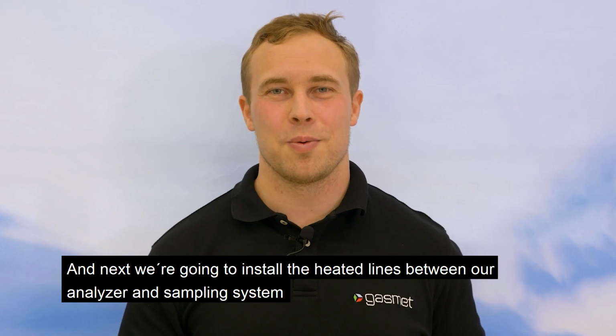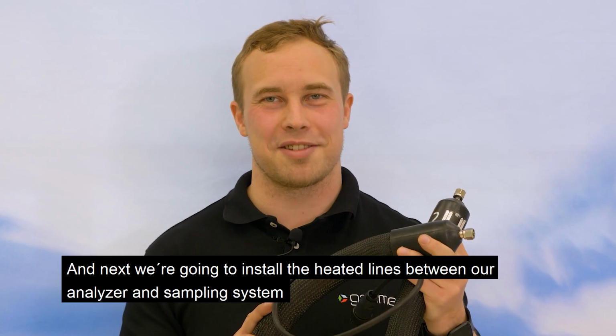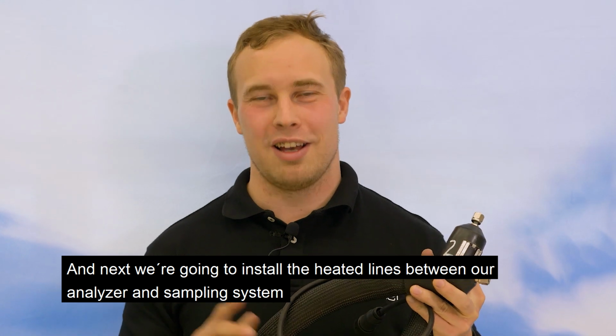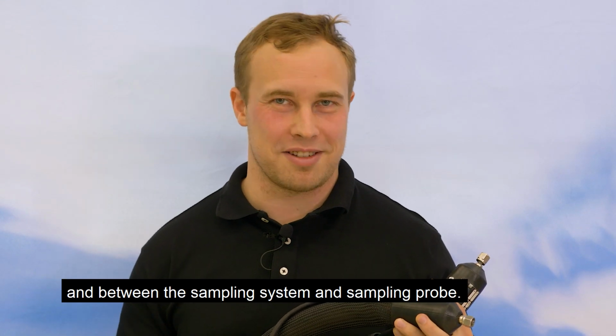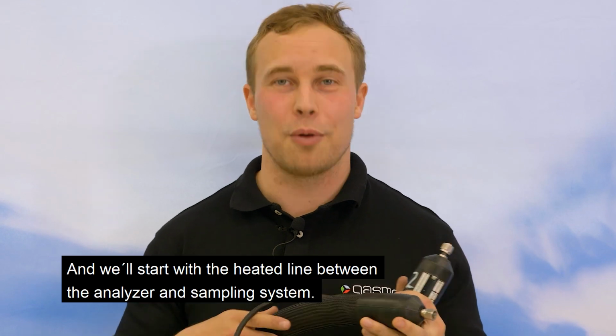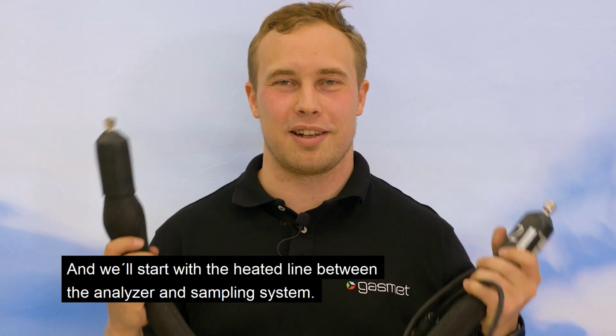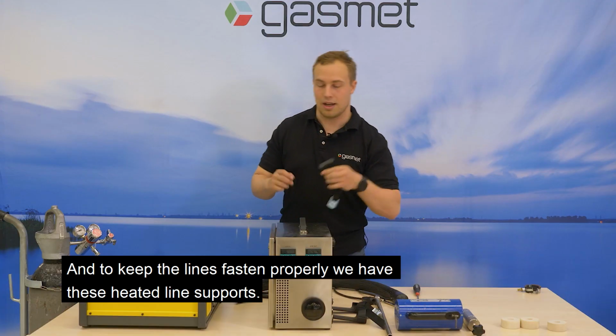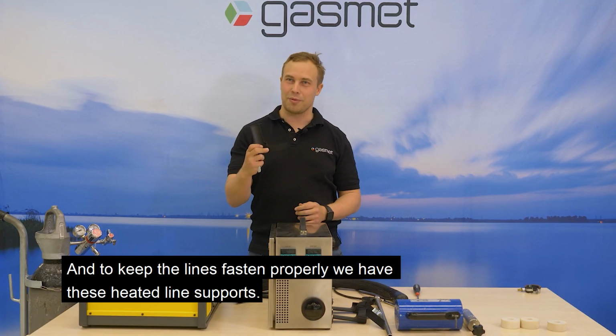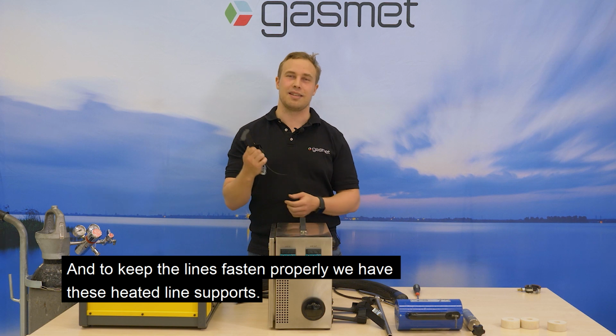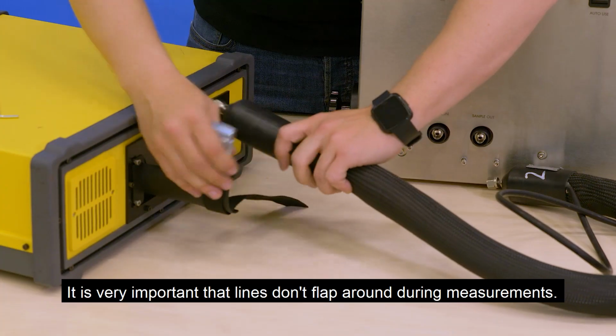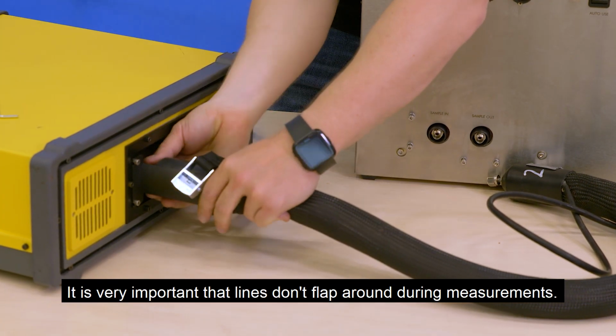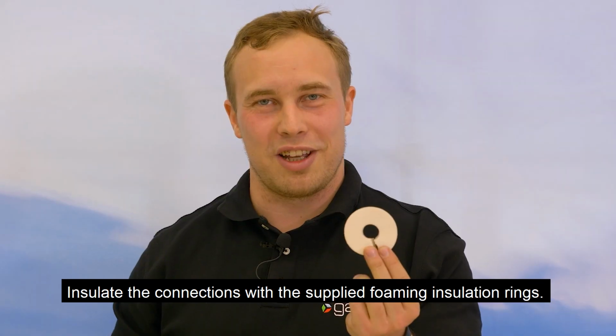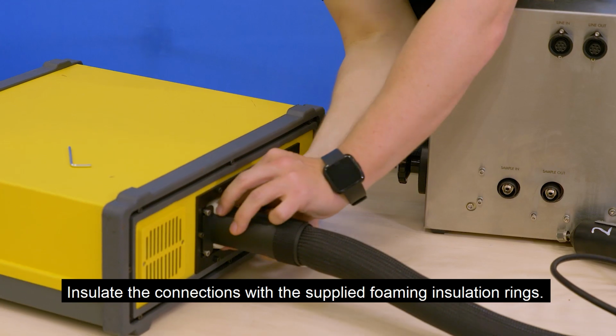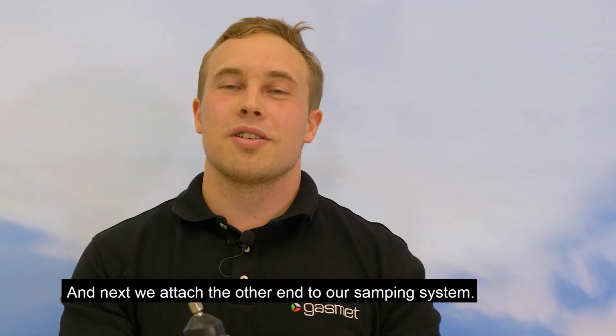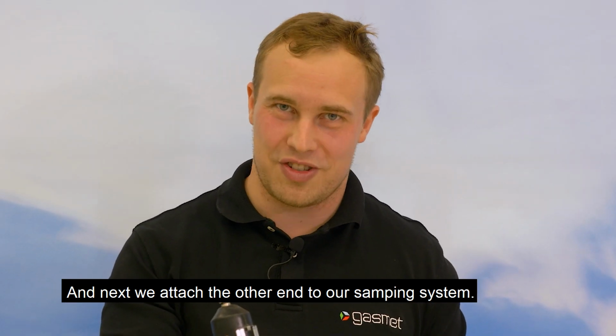And next, we're going to install the heated lines between our analyzer and our sampling system, and between the sampling system and the sampling probe. And we'll start with the heated line between the analyzer and sampling system. To keep the lines fastened properly, we have these heated line supports. You see, it is very important that the lines don't flap around when doing measurements. Insulate the connection with the supplied foam insulation rings. And next, we attach the other end to our sampling system.